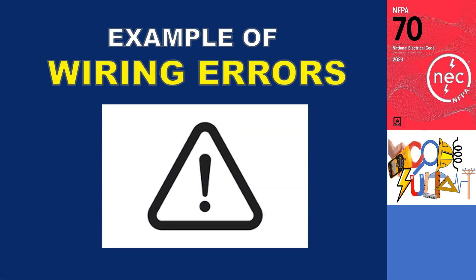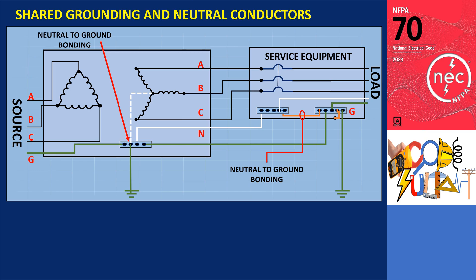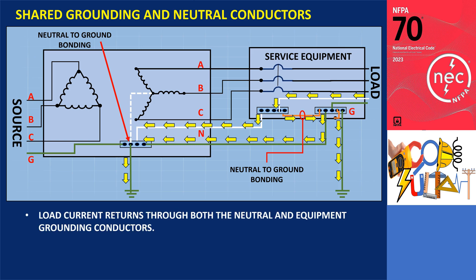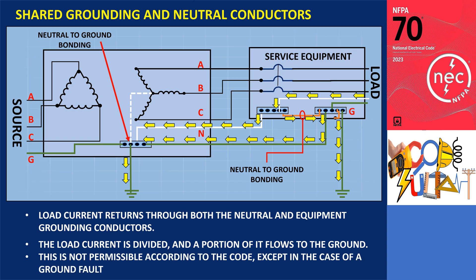Here are a few examples of wiring errors. Shared grounding and neutral conductors: in some wiring configurations, the grounding conductor and neutral conductor are shared or bonded together at multiple points. When the neutral is already bonded to the grounding terminal of the transformer and further bonded to the ground at the panel, a situation arises where the load current returns through both the neutral and equipment grounding conductors. As the grounding conductor is connected to all metal parts of the system, the load current is divided, and a portion of it flows to the ground. However, this is not permissible according to the code, except in the case of a ground fault.